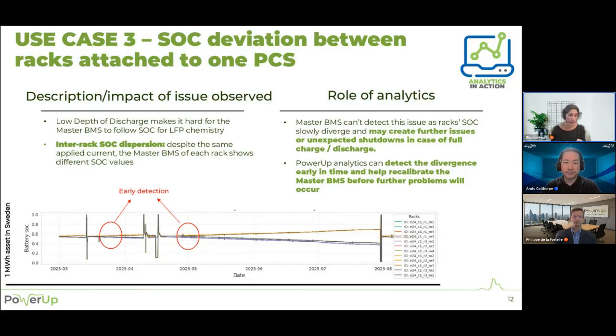So really, the tool is able to detect a small divergence and also to solve the issue, which is the most important point. It's possible then not to go to a shutdown, but to say, okay, here there is an issue, here we need to recalibrate the BMS so we start again on our good value. Because if we don't do it, it will diverge and there will be an issue. That's really an interesting point that we can do that.